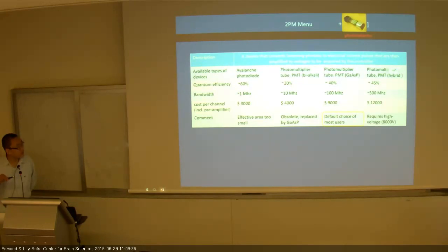It's called hybrid. Hybrid in the sense that it's still a PMT, but only one level of gain, combined with an avalanche photodiode. This one I didn't mention because it is not used so much in two-photon microscopy, in the sense that it has a very narrow limited bandwidth, so they respond relatively slowly. You need quite a long relaxation time. So the combination of this one with the PMT, which Hamamatsu creates, is to say, if you hear the word hybrid PMT or hybrid detector, it has an even slightly better quantum efficiency and very fast response time, and is very expensive. But they need high voltage to drive it, 8,000 volts. If you think of it, if you accidentally hit the voltage, it will really shock you.